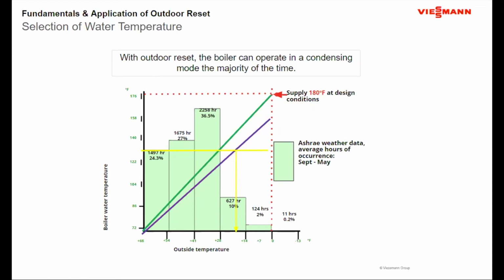Okay. And here's my supply at 180. Here's my return at 120. We do talk about condensing boilers, and we always talk about return water temperature. This yellow line across here, that's 130 degrees. Let's call that the dew point for my condensing boiler. What that really means to me is if my return water temperature is above 130, the boiler is not condensing. If it's below 130, it is condensing.